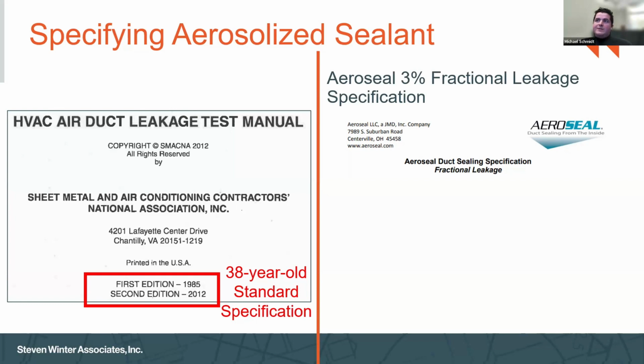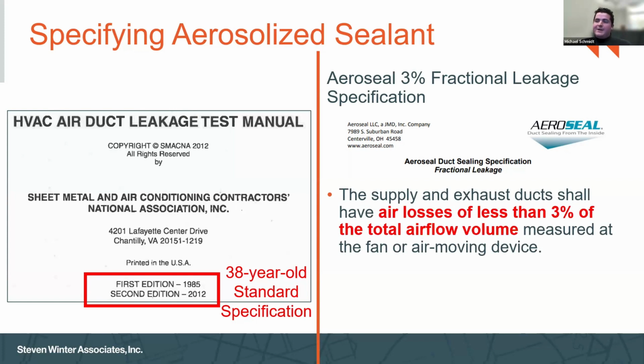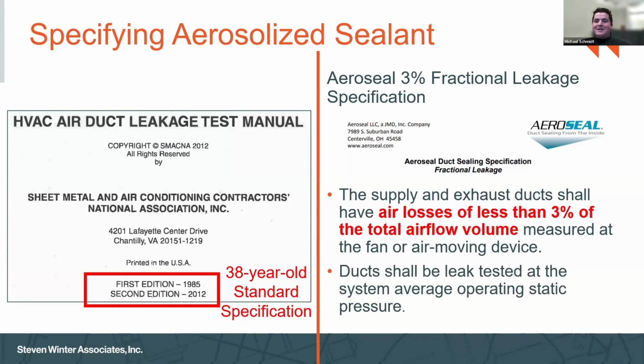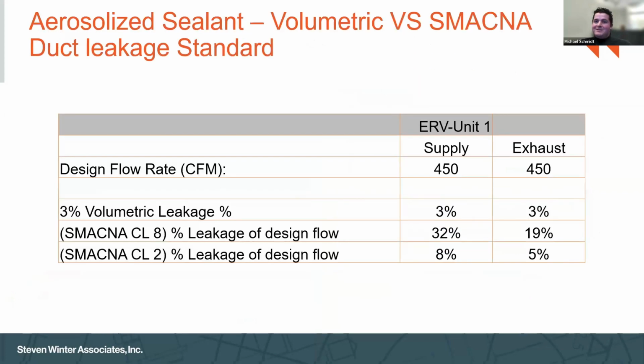I would recommend AeroSeal's 3% fractional leakage spec. I've pulled it out here. This comes directly from the manufacturer. You can find it on Google right now if you'd like, and it is a very effective way to get approximately 3% of that total air volume specified in your project, right? And just one more note on specifications: why are these so important? This is what really holds that contractor accountable for reaching the project goals, right? This is always leak tested at the operating static pressure of the system. So no to the left and yes to the right.